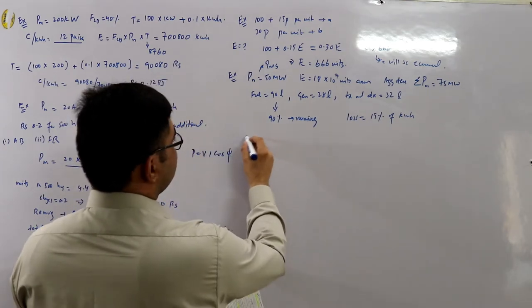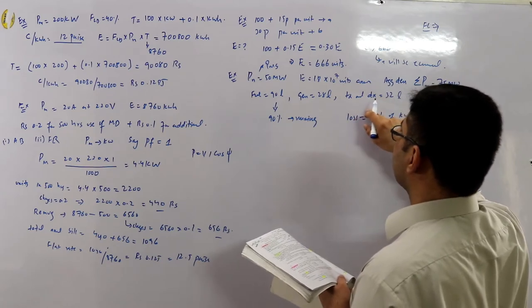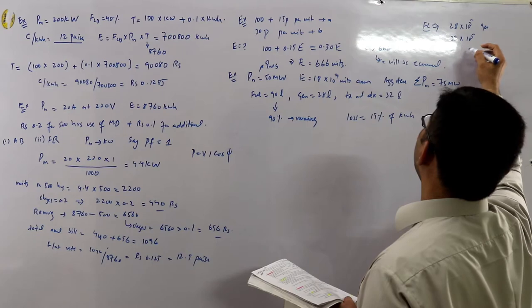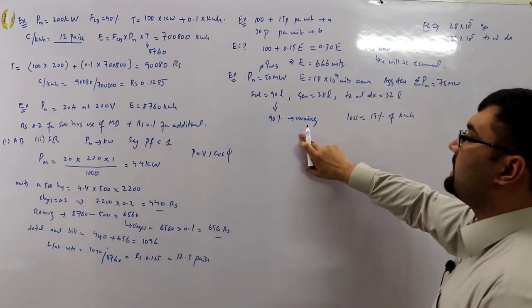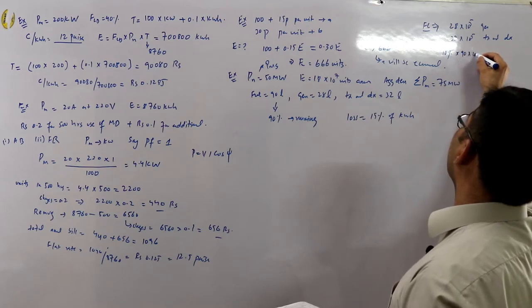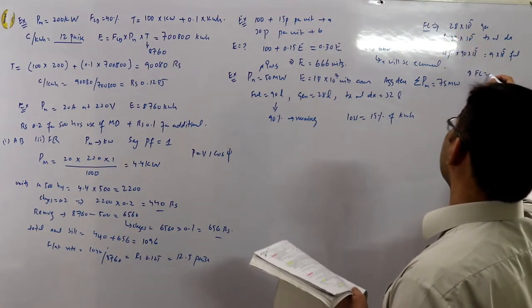Find annual fixed charges first. Fixed charges include generation cost (28 × 10⁵), transmission and distribution cost (32 × 10⁵), and 10 percent of fuel (9 lakhs). Total fixed charges = 69 lakh rupees.